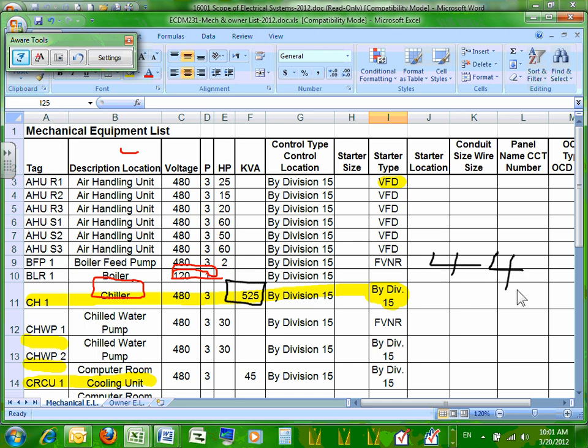As a matter of fact, if you go to Article 440, that's where the chillers are. It will tell you if you have a chiller with other loads, you take the largest multiplied by 125% of the chiller or the other load and add the rest of it. So you could easily assume the chiller is the largest load and add the rest of them to it. Yeah, let's assume that the chiller, even though I've given you KVA, is a motor.